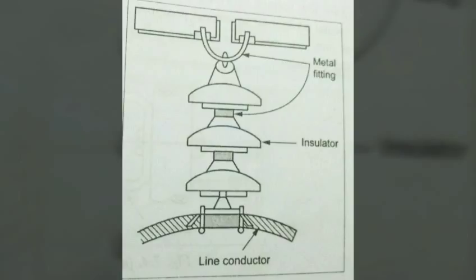The conductor is suspended at the bottom end of the string. The other end of the string is secured to the cross arm of the tower. The number of disks in series depends upon working voltage. Each unit or disk is designed for 11 kV. For 110 kV, it carries 7 or 8 disks. For 220 kV, it carries 13 or 14 disks.